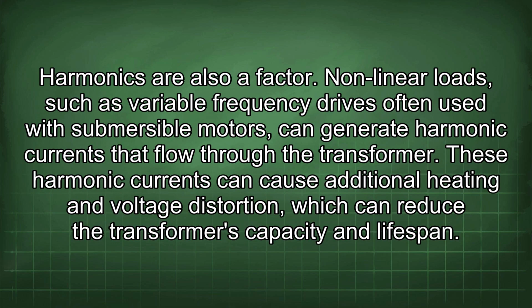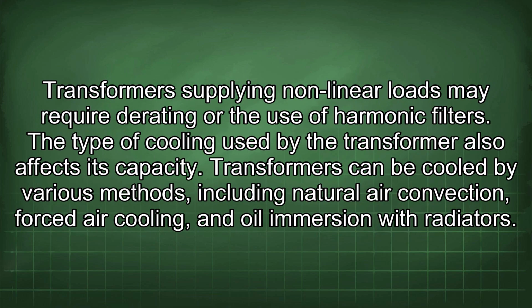Harmonics are also a factor. Nonlinear loads, such as variable frequency drives often used with submersible motors, can generate harmonic currents that flow through the transformer. These harmonic currents can cause additional heating and voltage distortion, which can reduce the transformer's capacity and lifespan. Transformers supplying nonlinear loads may require derating or the use of harmonic filters.